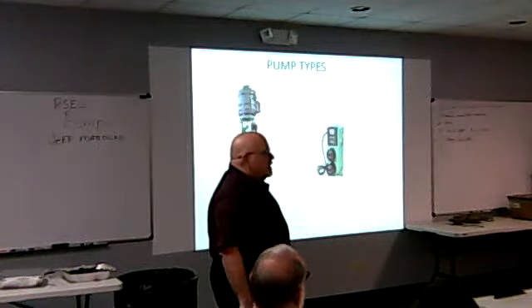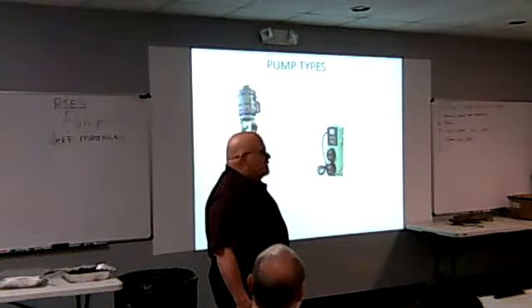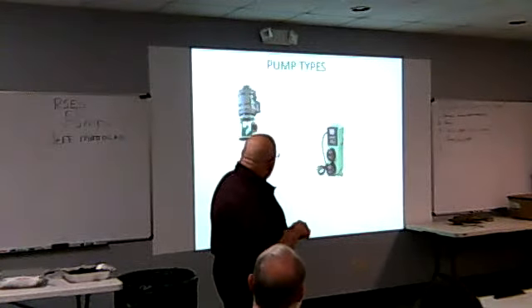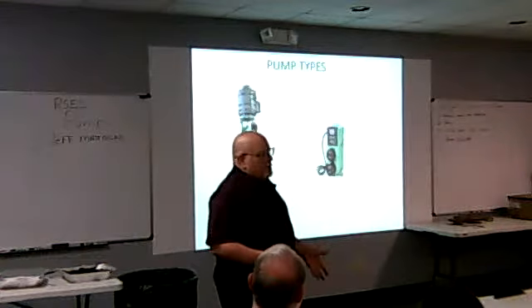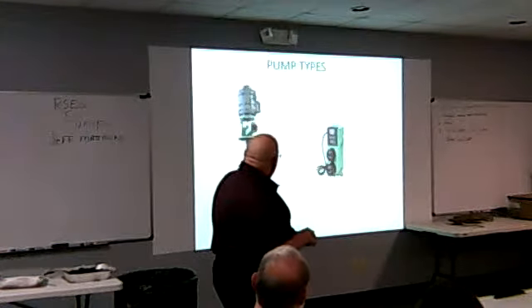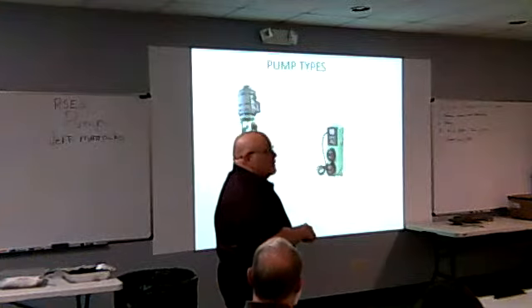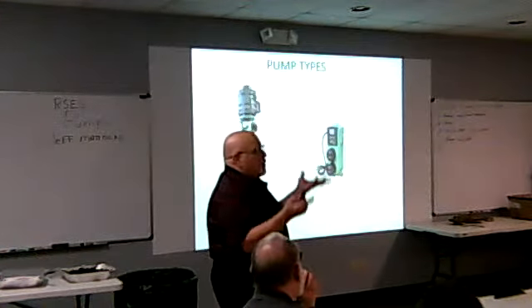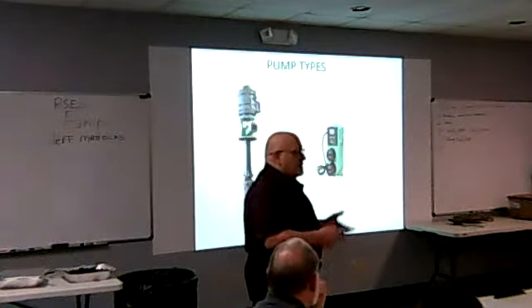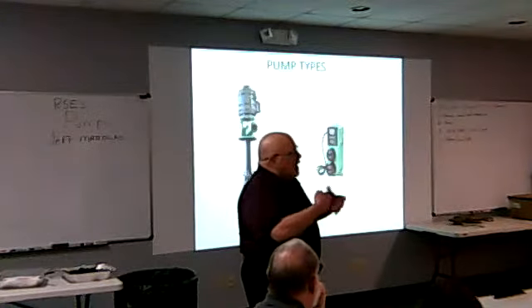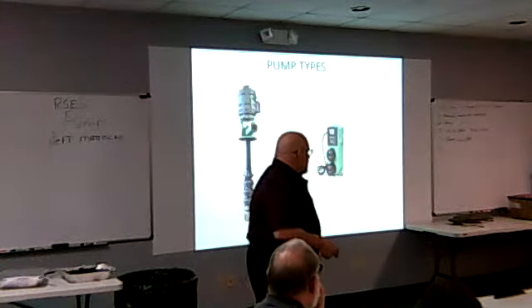Yes, sir. Use these for sewage too? They do, yeah, they can be used for sewage, but most time in sewage, I'm not really gonna touch on a lot of sewage tonight, that's a whole other story, but typically HVAC, these are enclosed impellers. Sewage usually has an open impeller, so if you get any strings or any garbage in there, they don't clog up the impeller. Yeah. So that's a good time to show this too.